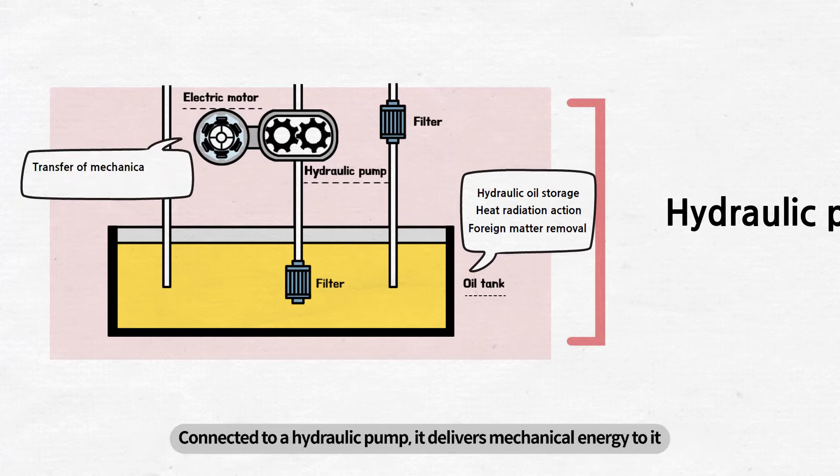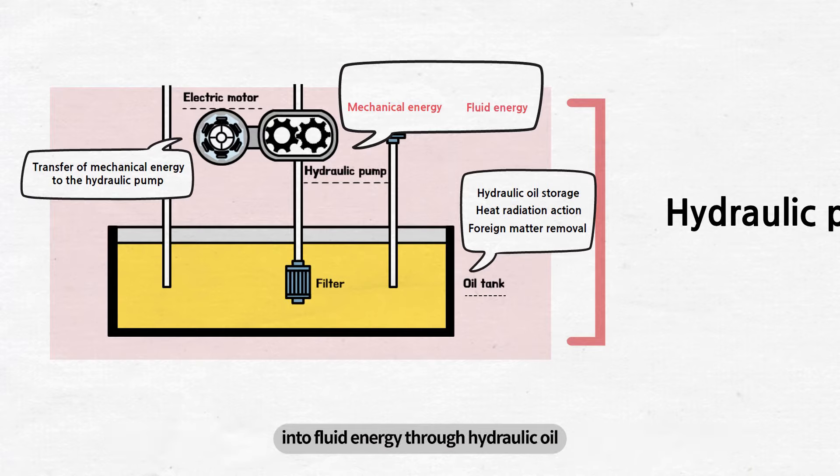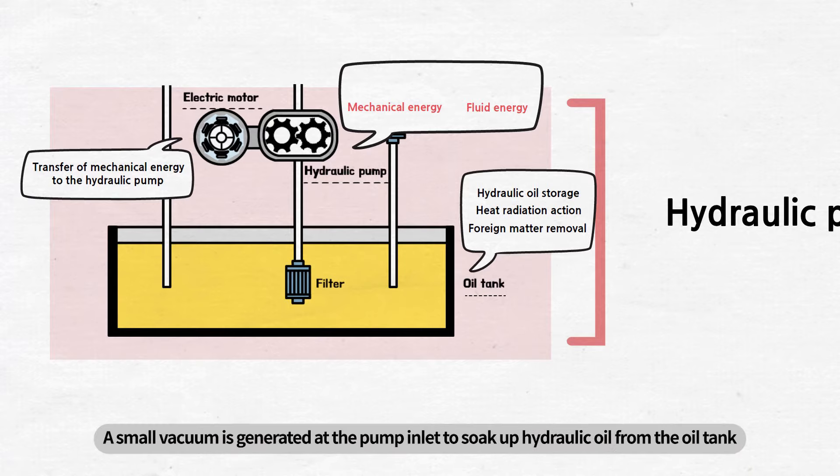A hydraulic pump is what converts mechanical energy supplied by an electric motor into fluid energy through hydraulic oil. A small vacuum is generated at the pump inlet to soak up hydraulic oil from the oil tank, while generating high-pressure oil using the rotational motion of the internal components.